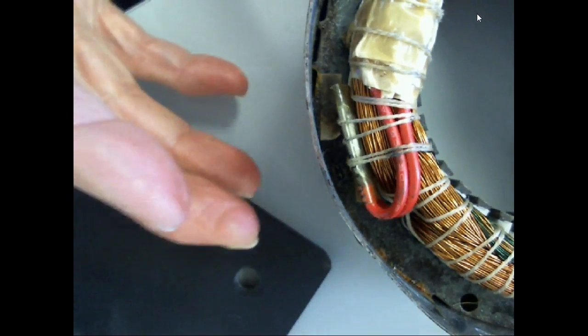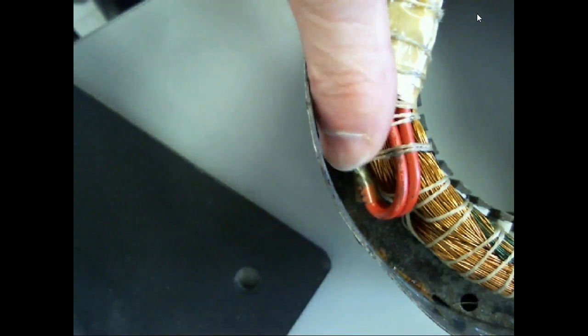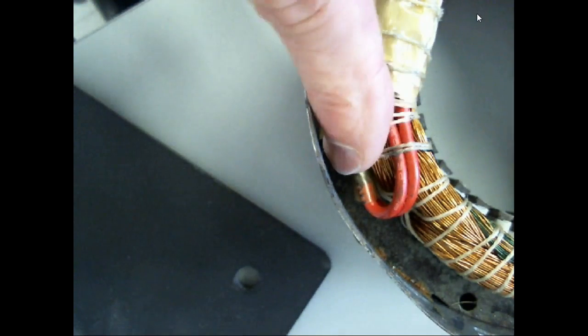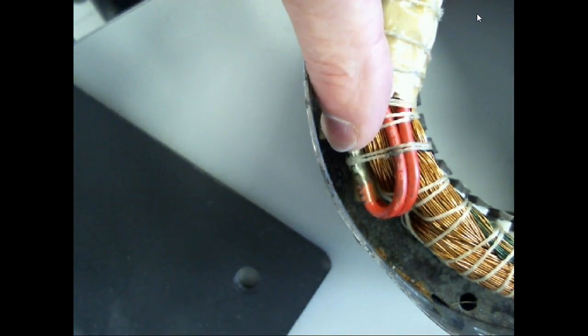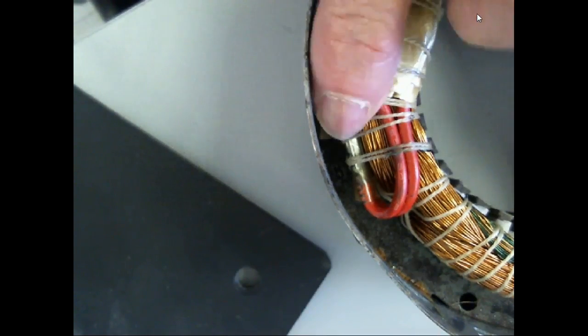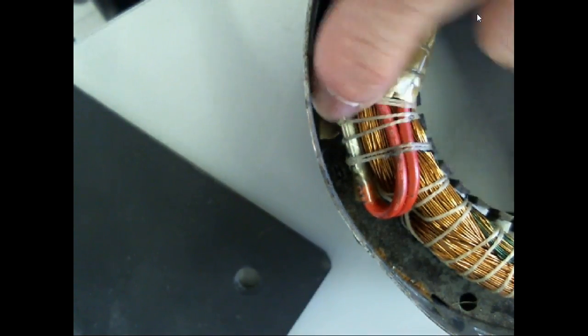Here's the overload right here. See the red? The little thermal switch right there, that's the overload. So the overload is going to let the motor start, but if the motor doesn't start right or something stalls it, then the overload is going to open. And it's a little thermal switch. This gets people in trouble because this motor's sitting there not running, and they think something's going on. They get their hands in there, they don't disconnect it, and then the overload automatically seals back up on you, right? You understand? And most of your little single phase motors are going to have this internal overload.